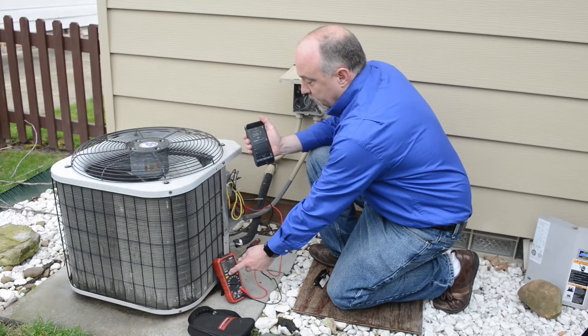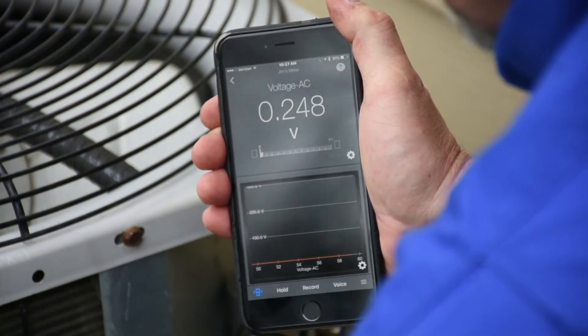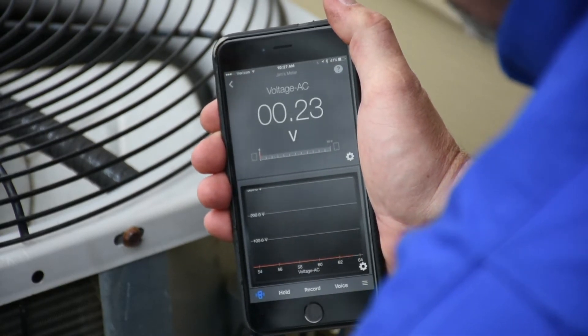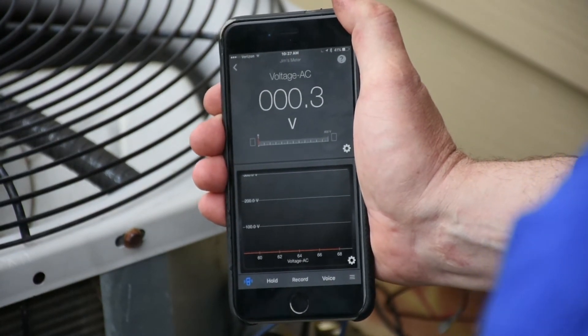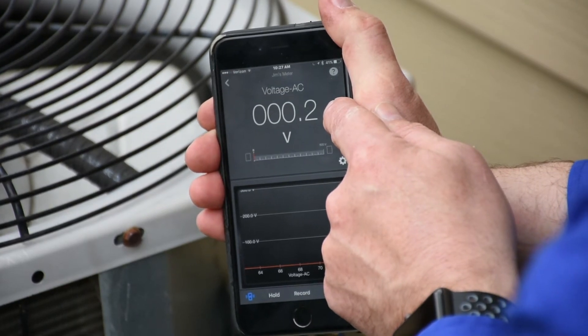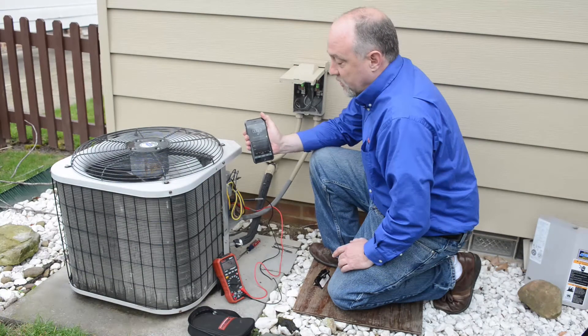I'm going to hit the range key on the meter, and when I hit that key, I'm going to change the scale. Now I'm going to change it again — now we're at the 60-volt scale. Change it again and I'm at the 600-volt scale, and now you can see that is only about 2 tenths of a volt on the display. So we actually have zero volts.